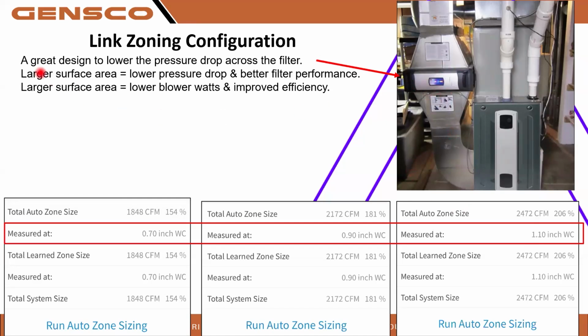Then over the airflow, the larger surface area equals lower pressure drop and better filter performance. So larger surface area equals lower blower watts and improved efficiency. So we get better comfort and improved efficiency. So let's increase those filter sizes. That's not going to hurt anything.